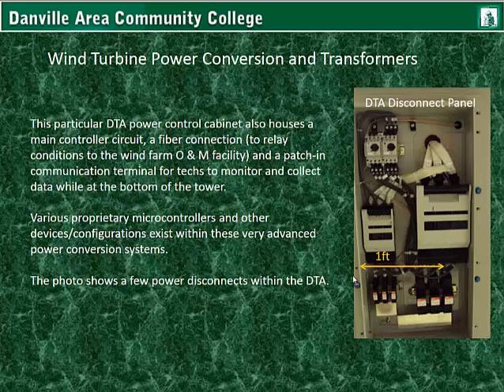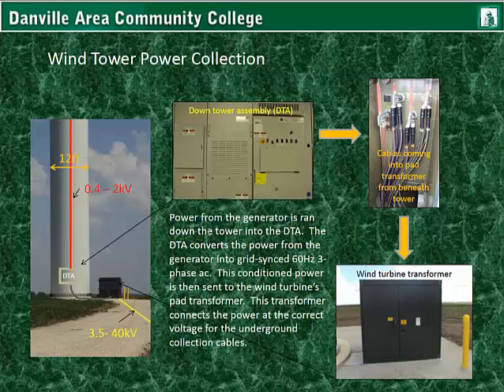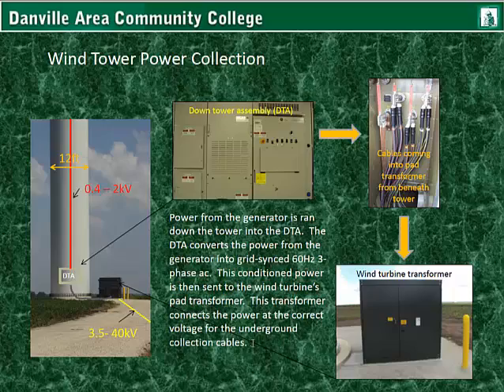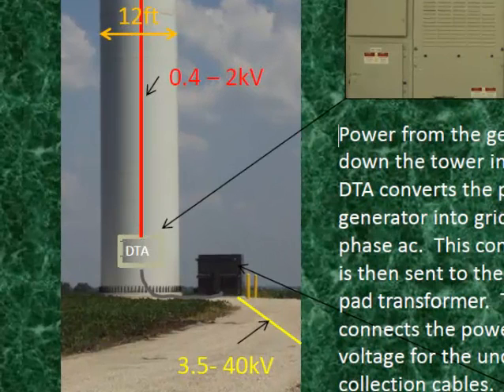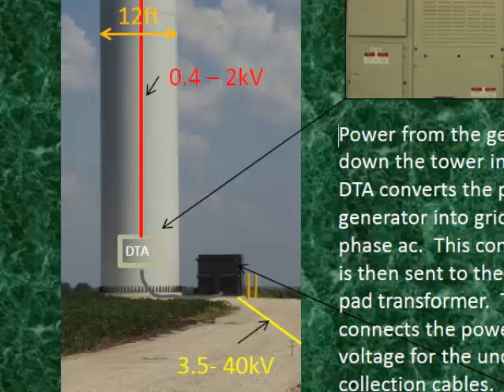This photo shows a few power disconnects within the down tower assembly. Power from the generator is run down the tower into the DTA. The DTA converts the power from the generator into grid-synced 60 Hz three-phase AC. This conditioned power is then sent to the wind turbine's pad transformer. This transformer connects the power at the correct voltage for the underground collection cables, where it is stepped up.